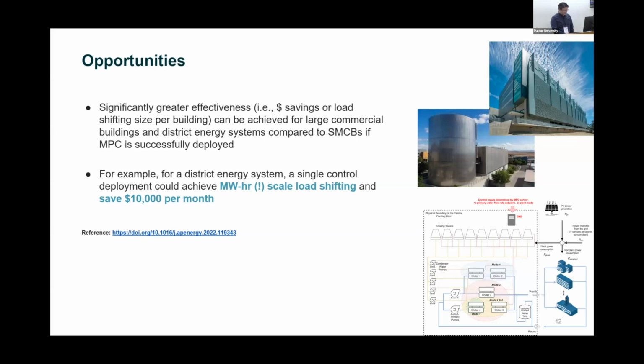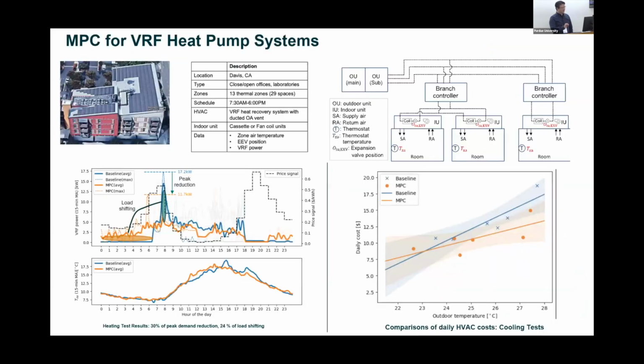Let me skip this, although I wanted to emphasize, one of the buildings that we have covered is a VRF system, having all the refrigerant flowing into the indoor coil rather than an air handling unit. So we developed the model predictive control for the VRF system. And this heat pump provides heating and cooling during summer and winter. And it shows, again, the load flexibility and the daily cost savings in response to the price signal.